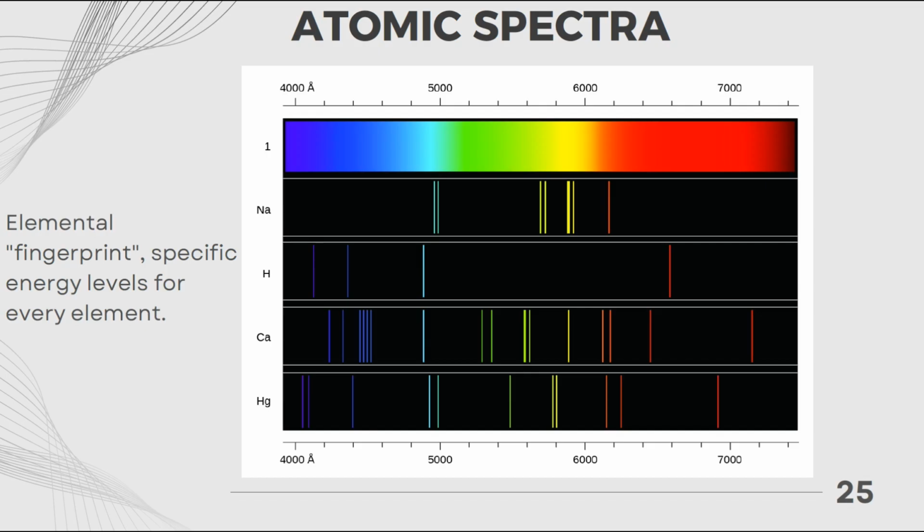It gives you some specific sodium radiation, sodium wavelength. You catch them, register them with a sample. Then you follow the absorbed light, because sodium in the sample will absorb light which is emitted with a sodium lamp. So you need a specific lamp for a specific element.